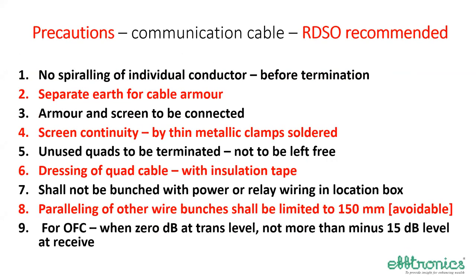Now about the armor and all, we will see just a little later after two slides. No spiraling of individual conductor before termination. What is spiraling of conductor? While terminating at a terminal, to avoid pressure on the terminal and to keep some looseness, normally the conductor is bent in a spiral way. It is not permitted for the axle counter cable because it is carrying high frequency digital data, so it can distort the signal.